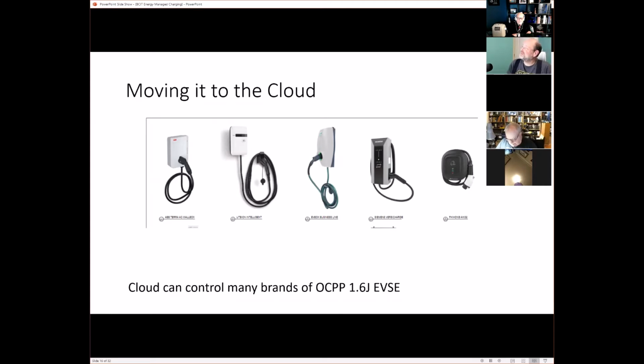And I was very dubious about it at first. I was really scared that we were going to start tripping breakers. Matthew Luce was a great help on this, coming up with an idea that would allow us to do this. And so moving it to the cloud, we're not stuck with using just Clipper Creek chargers anymore. We can use anybody's OCPP chargers as long as they support a full set of the commands that OCPP 1.6 makes available. And that would make a lot of people happy, because now you can use the Lightning or the ABB or the EV Box, and you can mix and match. So you don't need to have everybody's EV charger in the parking lot the same brand. Maybe they don't like the Lightning product, or the VersaCharge might be too expensive, and so everyone could buy their own charger and we could connect it to the system.